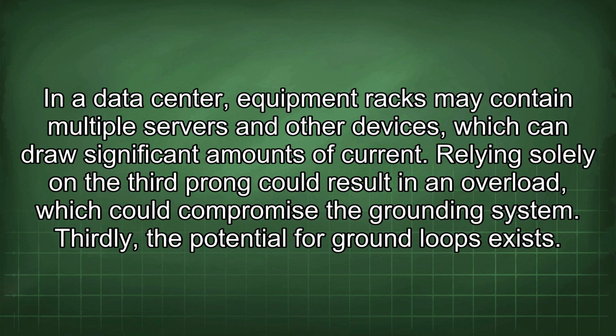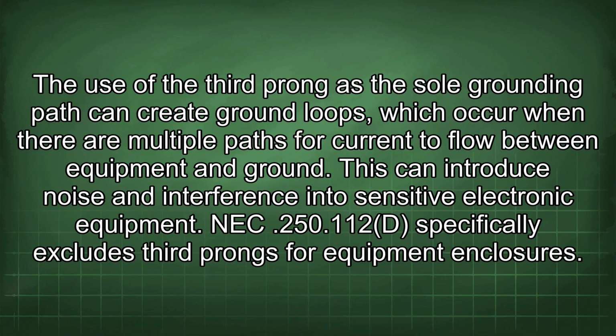Thirdly, the potential for ground loops exists. The use of the third prong as the sole grounding path can create ground loops, which occur when there are multiple paths for current to flow between equipment and ground. This can introduce noise and interference into sensitive electronic equipment.